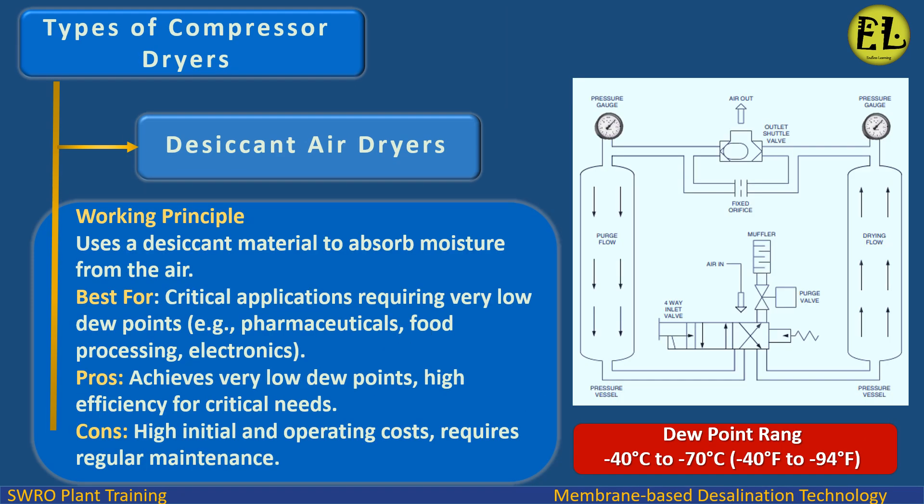Desiccant air dryers. Working principle: uses a desiccant material to absorb moisture from the air. Best for critical applications requiring very low dew points, e.g., pharmaceuticals, food processing, electronics. Pros: achieves very low dew points, high efficiency for critical needs. Cons: high initial and operating costs, requires regular maintenance. Dew point range: minus 40°C to minus 70°C (minus 40°F to minus 94°F).